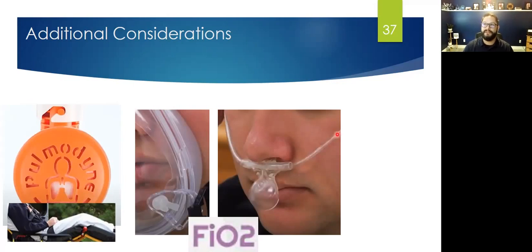Obviously, first step is to turn on your cannula and your capnography CO2, and you can move that up to upwards of 5 liters a minute. Again, something I didn't know before I came here. It's not like a normal nasal cannula where you go up to 6. This only allows you to go up to 5. So that's the first step. And by doing that, you can get this FiO2 up to somewhere in the 40, 41, 42% range.